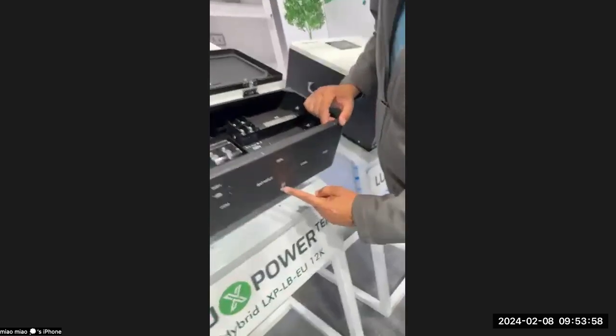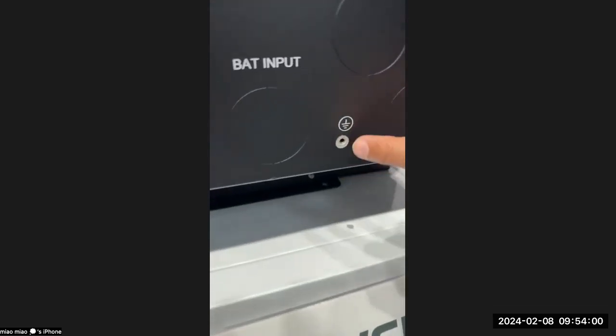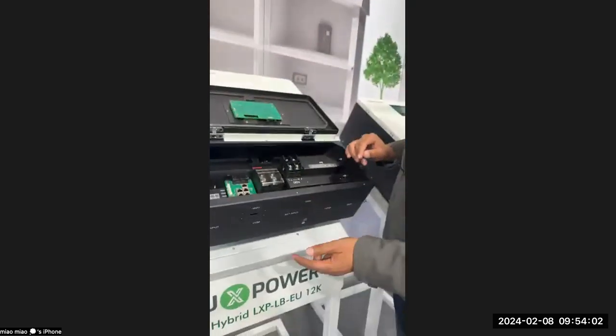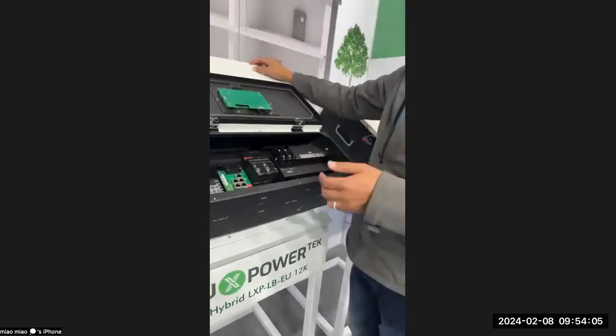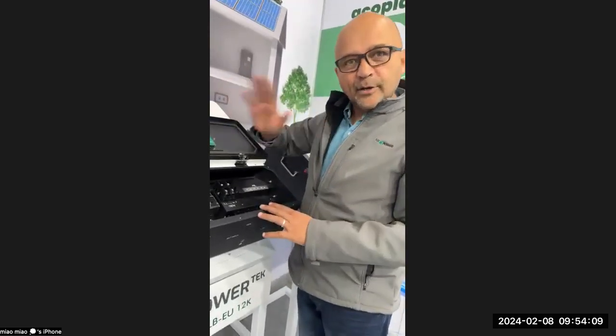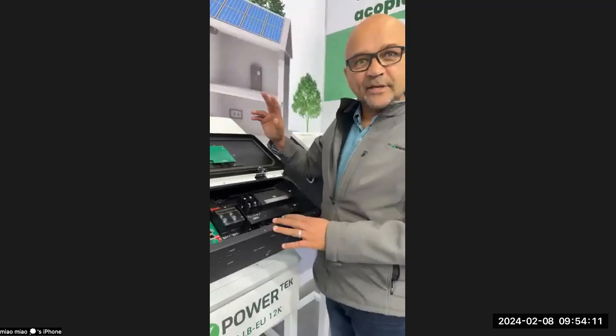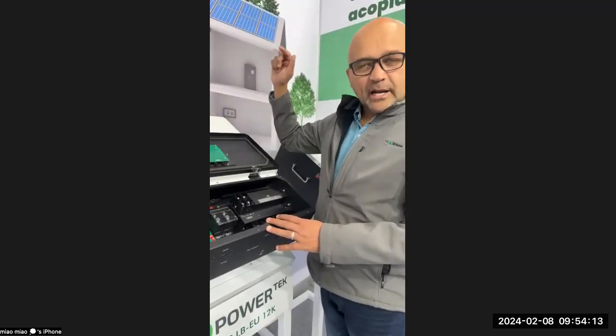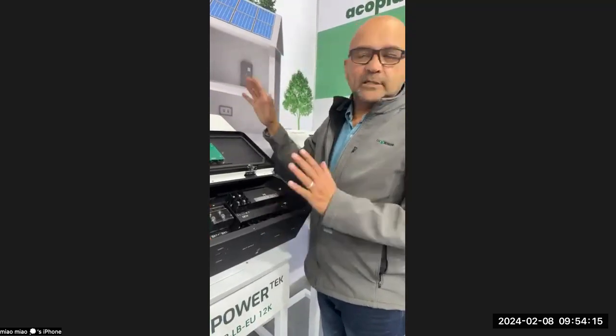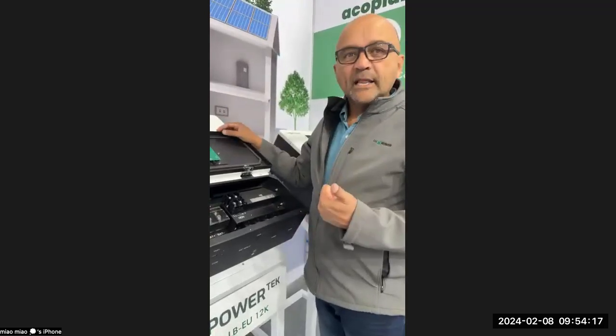You'll see it here. Every machine of ours has an earthing point. Very important to earth your machines. I cannot stress the importance of earthing enough. Run your earthing. You need to earth the living daylights out of your installation. Earth the rails. Earth everything so that you can. Number one, it makes it SANS compliant, and number two, it makes it safe.